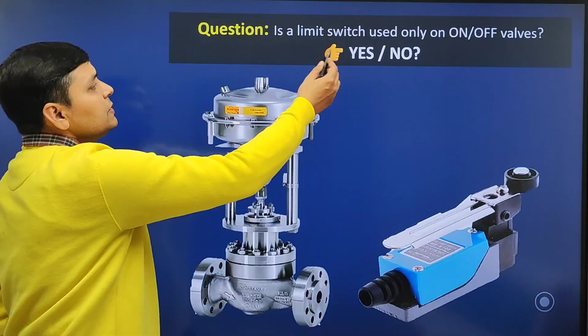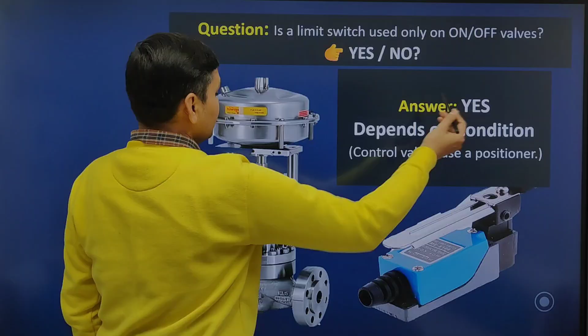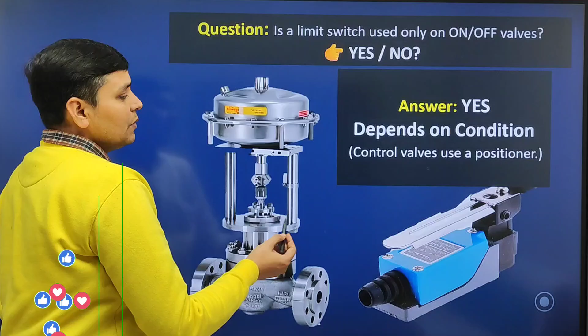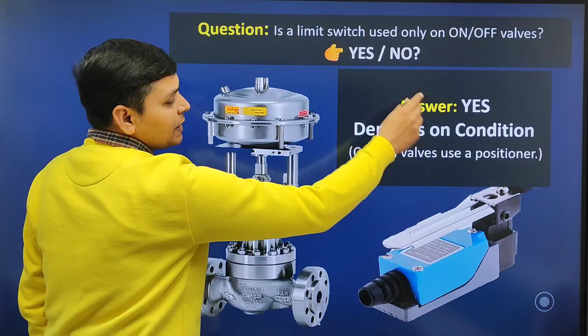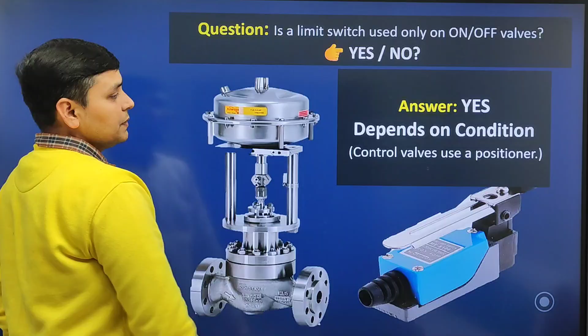Next question, is a limit switch used only on on-off control valves? The answer is yes, but it depends on the condition. If we are using globe type control valve for on-off applications, then we use this limit switch. We use this limit switch as a positioner. If control valve remains fully open, it will give the signal for on position, and if control valve is fully closed, it will give the signal for off position. But friends, in case of butterfly valve or in case of ball valve, we use a pneumatic actuator. You will find on and off indication on the pneumatic actuator itself.